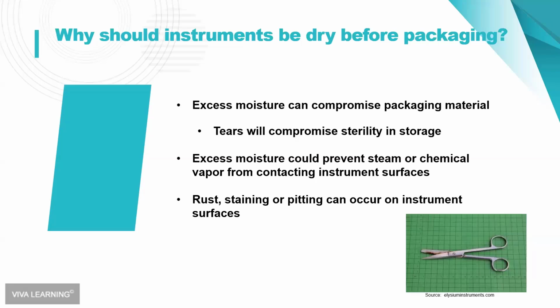Now, you can buy commercially available instrument dryers. They're FDA cleared instrument dryers, or you can do something very simple like let the instruments sit and air dry before you package them and before you wrap the cassettes to put them in the sterilizer. And another quick way to do it is to have a container that has 90% isopropyl alcohol. Alcohol is a desiccating, a drying agent.